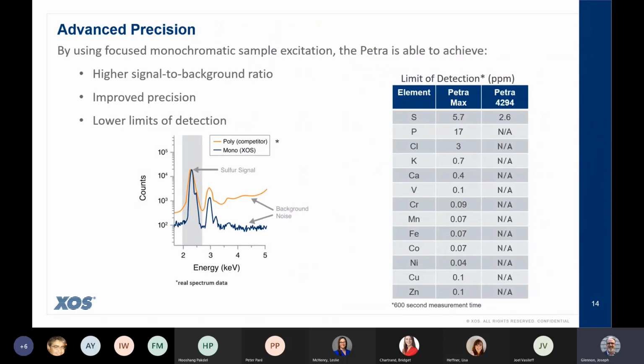So what are we able to achieve with the Petra with this advanced precision? We have a higher signal-to-background ratio, improved precision, and lower LOD. You can see the difference in the chart: the orange is polychromatic with our competitors' traditional XRF, and the blue is the monochromatic excitation that XOS has. So a much different signal-to-noise ratio. On the right, there are those LODs again for all of the elements.